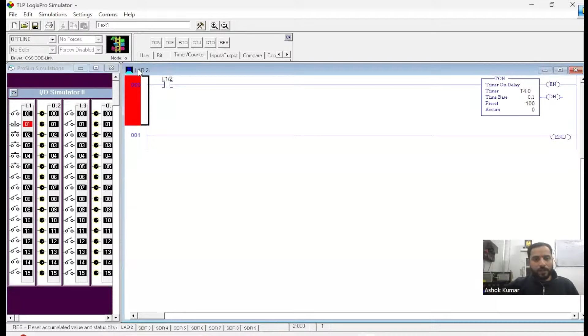If we do this, the timer will run only as long as you hold the input — the timer also needs continuous current to stay on. Let me show you: if I tap it once, the timer runs, but if I release it, the timer turns off. Here I'm tapping, the timer is continuously working, but if I release it, the timer is off. So the timer won't work if we don't hold the button. To hold it, we either need a toggle, or if we don't have a spare toggle, we need to use start-stop logic.